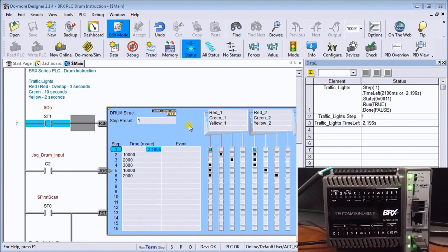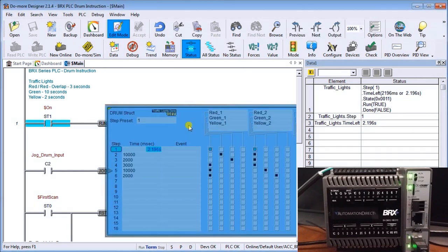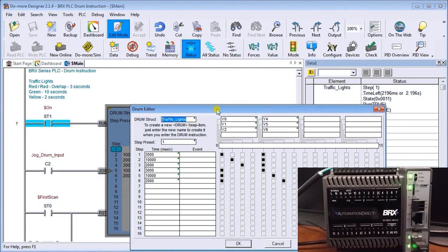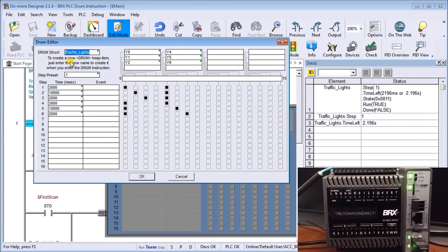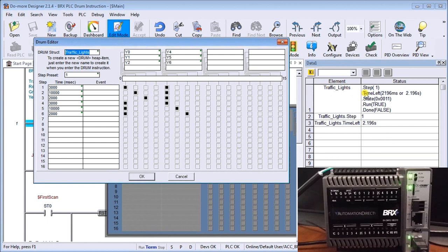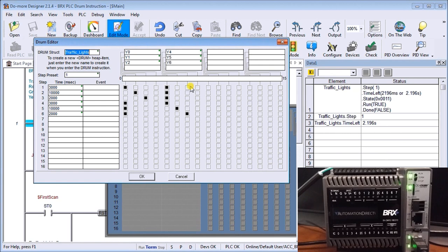So if we look at this instruction itself, we will set up our drum heap instruction, which we call traffic lights. What this will do is automatically reserve a bunch of different parameters that we can set for our drum itself. And if you look over here, those heap instructions will set the step, our time left, our state, our run, and our done. So we can monitor all those elements for our drum itself.